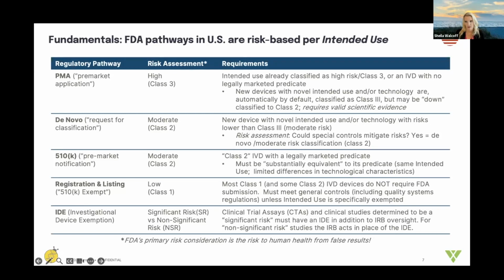So if you have a class 3 device, you cannot market it without submitting a PMA and getting that approval from FDA. The next is a de novo, and sometimes people call it a de novo 510K, but really, as I said, by default, under the law, everything is class 3 unless it's down classified, and FDA has in recent years really increasingly used de novo applications. It's a request for down classification, essentially, or request for classification for moderate risk devices with novel intended uses.